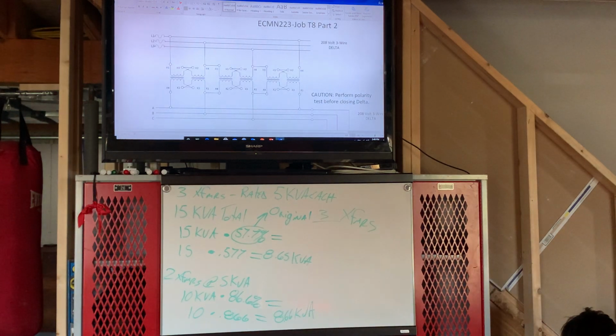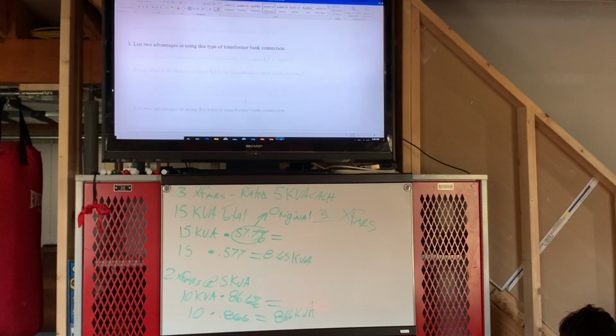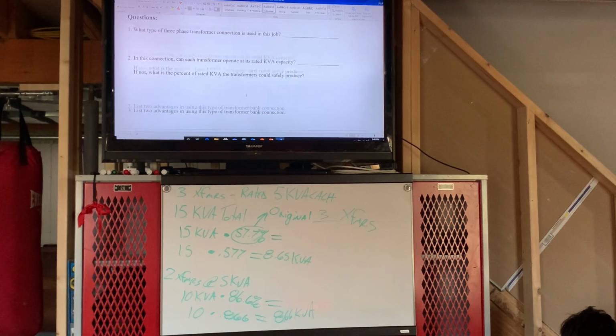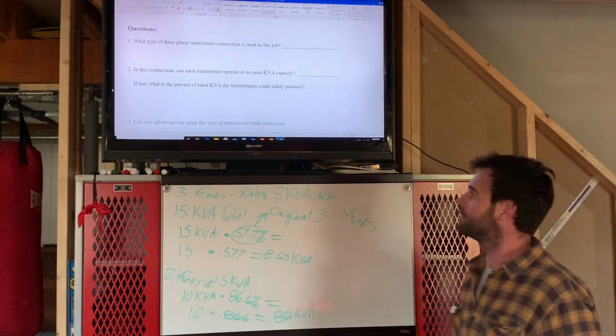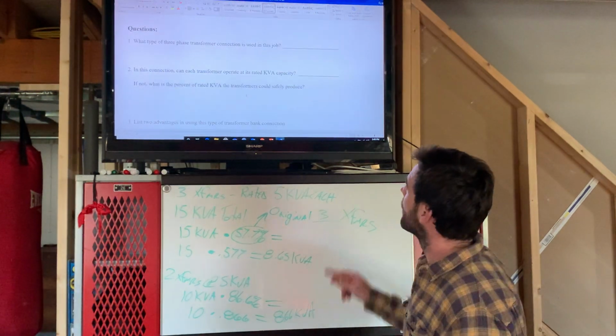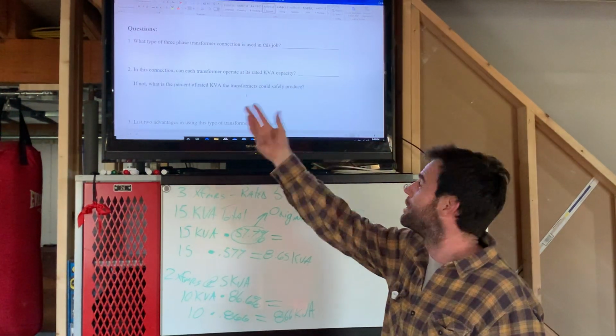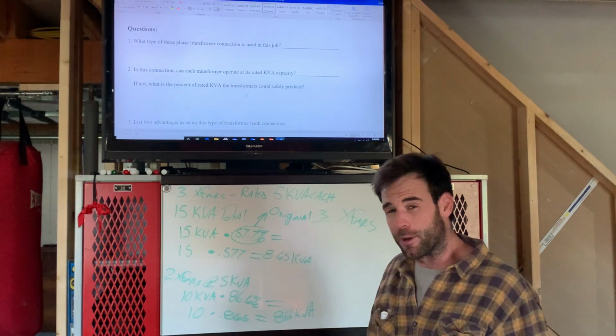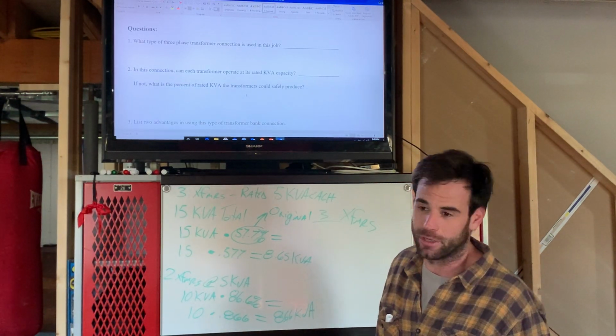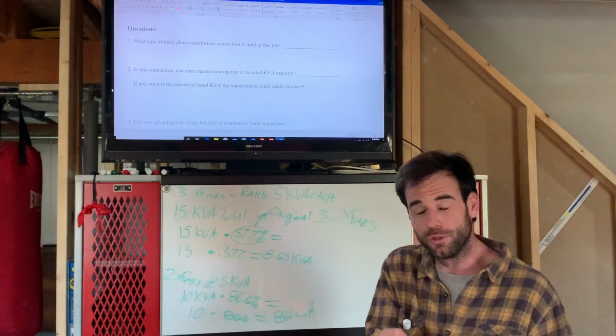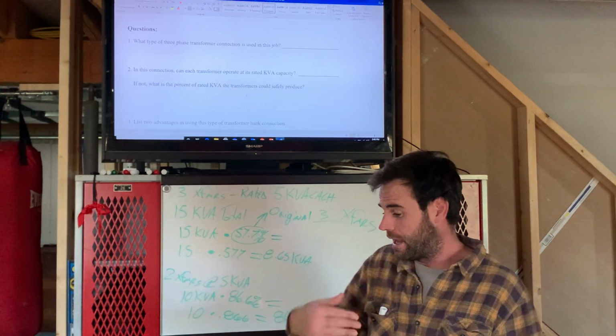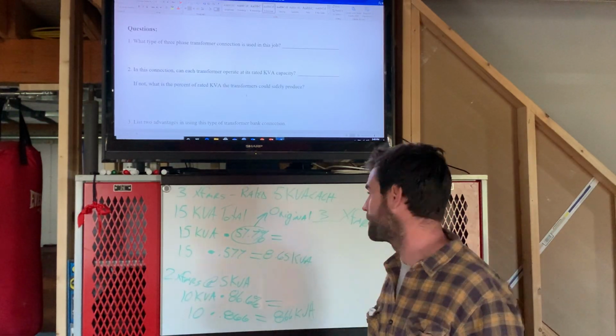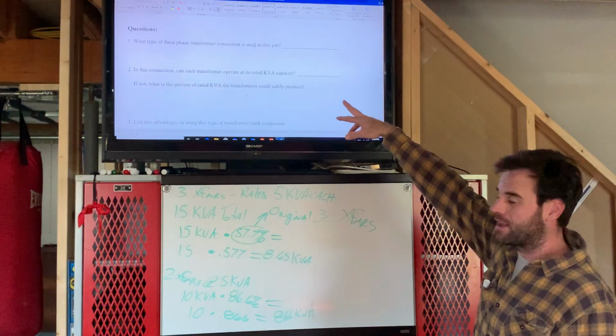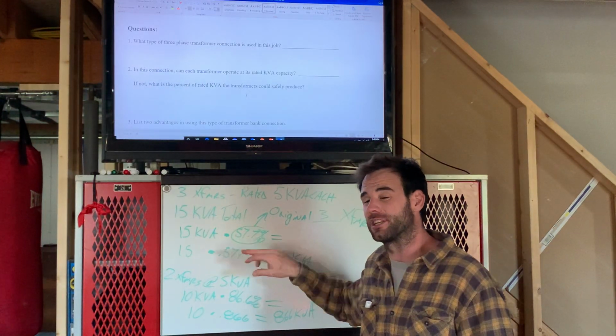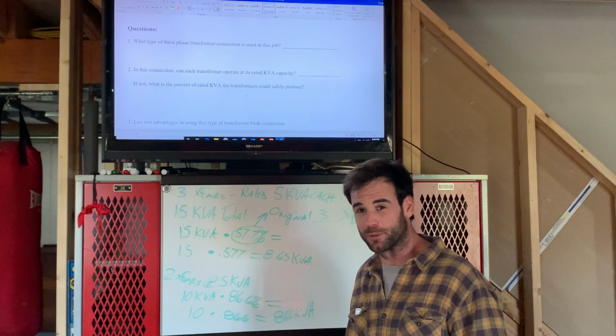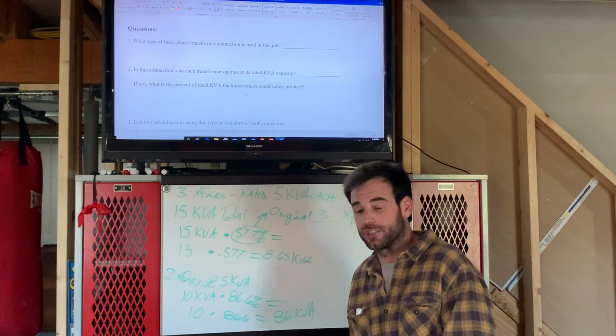Any questions on this job I'm uncertain of? Right here, these 3 questions, we just answered these questions. All right, what type of transformer bank connection is this used? It's an open delta. In this connection, could each transformer operate at its kVA capacity? No, it cannot, because you're asking 2 transformers to perform the work of 3. The only time they're all going to operate at their full kVA is in part 2 when we have 3 transformers in there. If not, what is the percent of the kVA that you can use? You're going to say 57.7% for 3 transformers or 86.6% for 2 transformers, and list 2 advantages of this.